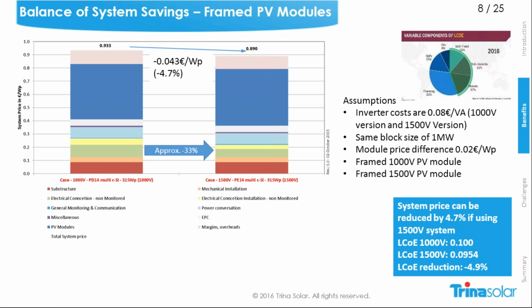So if you compare this on a complete system level, then in this example we have a cost reduction of 4.3 euro cents or 4.7%. If you now take a look here at the LCOE, and you have, for example, a location in the south part of Germany or in London, where we have an energy yield of, let's say, 1000, or in London it's more in the direction of 950, or if you go to South Europe then 1200, but if you now stay at 1000 kilowatt hours per kilowatt peak, then we will have an LCOE of approximately 10 cents with the 1000 volt system.